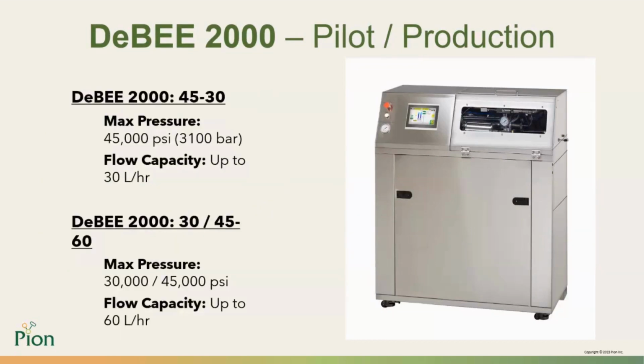Pion offers multiple variations of the DeBEE 2000, primarily with differing flow rates. One variation is referred to as the DeBEE 2000 45-30. The maximum process pressure for this unit is 45,000 psi with a flow capacity up to 30 liters an hour. The DeBEE 2000 30/45-60 has a maximum processing pressure of either 30,000 or 45,000, and the flow capacity for this model will be 60 liters an hour.